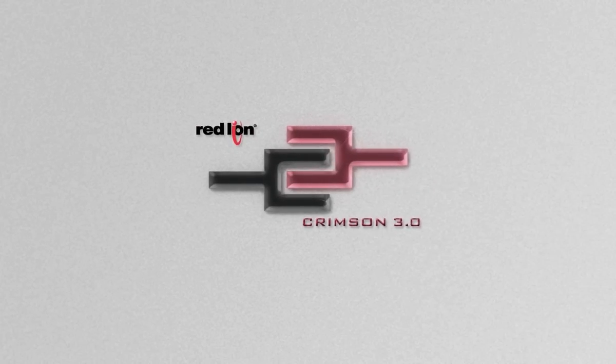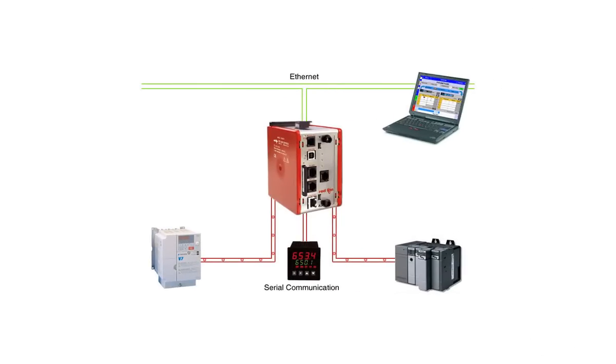In this video, I will show you how to do protocol conversion using Red Lion's Crimson 3 software and our Data Station Plus. In this example, we'll say we have an Allen Bradley PLC that only has an RS-232 port, and we want to expose that information as Modbus over Ethernet to a SCADA system running Modbus TCP/IP. For our purpose here, we'll assume the SCADA is the master, so we want our Ethernet port on the Data Station to be a Modbus slave.